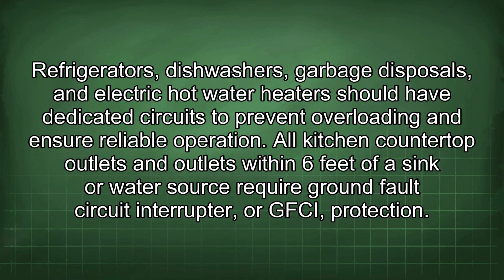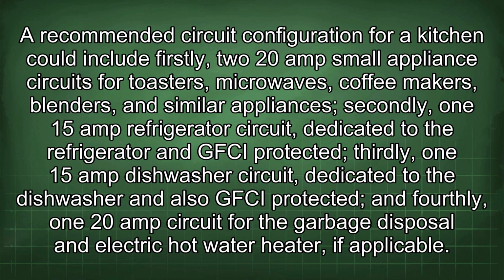All kitchen countertop outlets and outlets within 6 feet of a sink or water source require ground fault circuit interrupter, or GFCI, protection. A recommended circuit configuration for a kitchen could include, firstly, two 20-amp small appliance circuits for toasters, microwaves, coffee makers, blenders, and similar appliances. Secondly, one 15-amp refrigerator circuit dedicated to the refrigerator and GFCI protected. Thirdly, one 15-amp dishwasher circuit dedicated to the dishwasher and also GFCI protected. And fourthly, one 20-amp circuit for the garbage disposal and electric hot water heater if applicable.